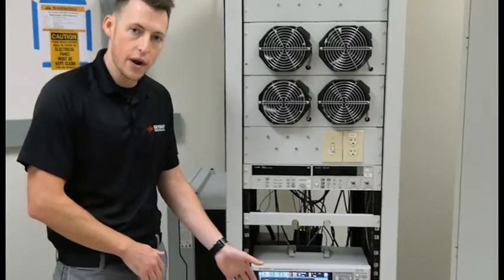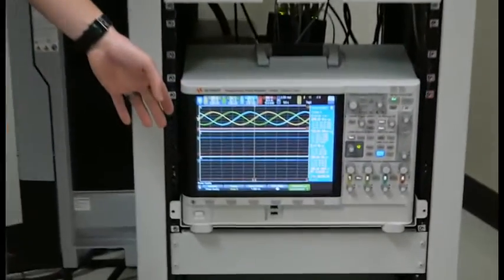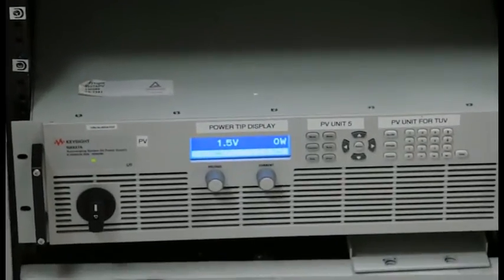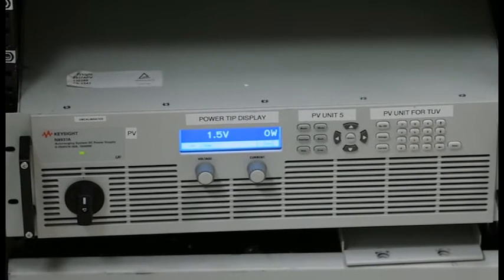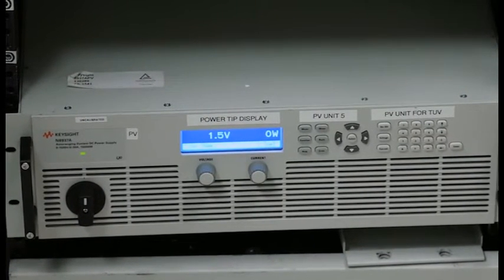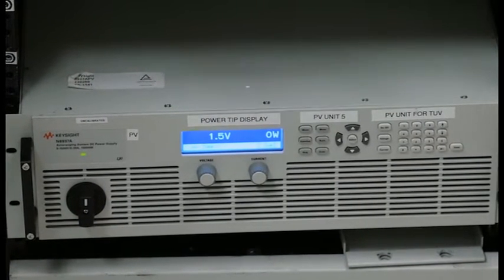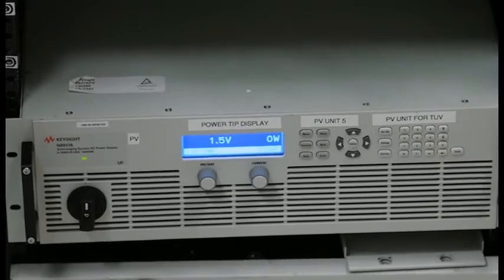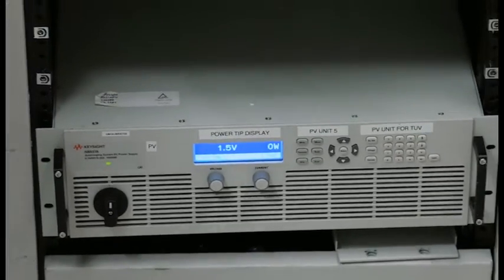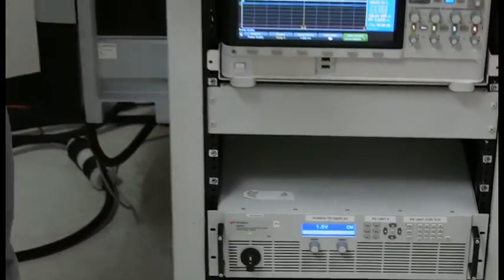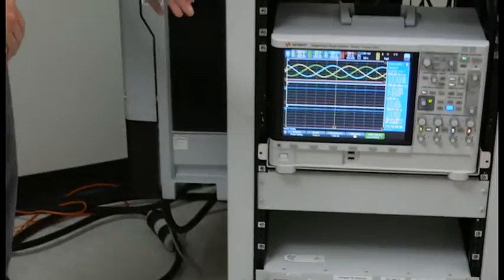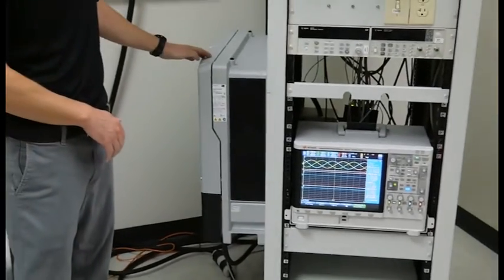Down here at the bottom of the rack you'll see that we've got a 15 kilowatt N8900 APS power supply. This has advanced solar array simulation capabilities as well as it works as an auto-ranging power supply. You'll see here on the side of the rack that we have it connected to a 12 kilowatt SMA inverter.